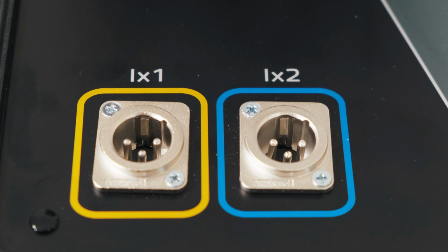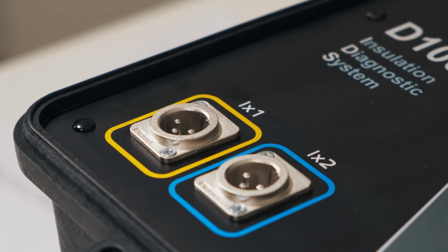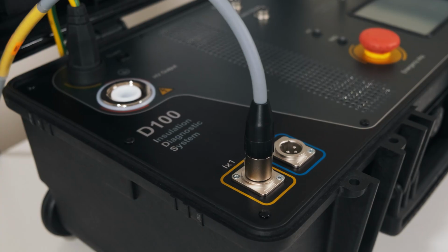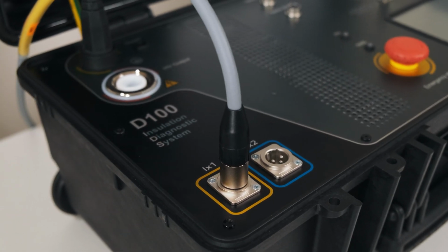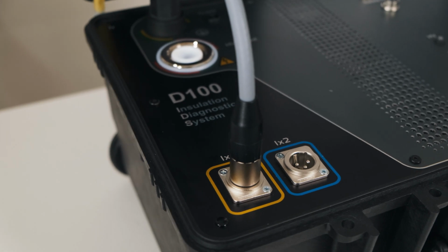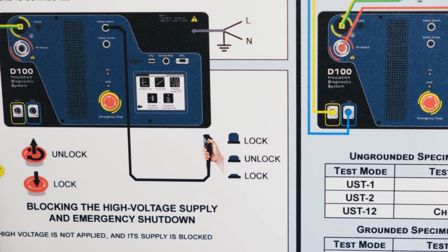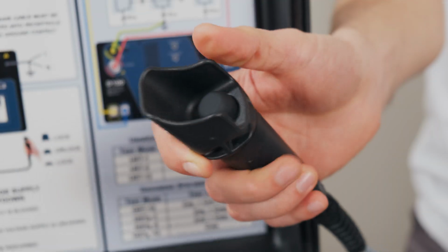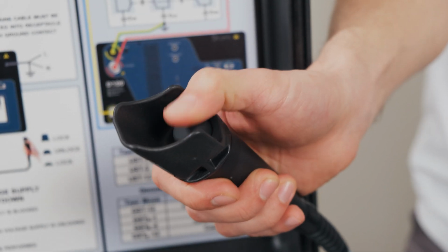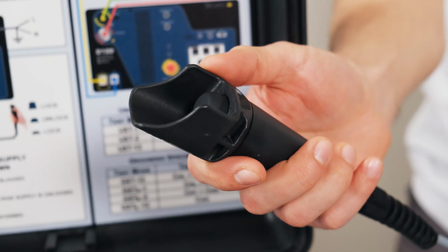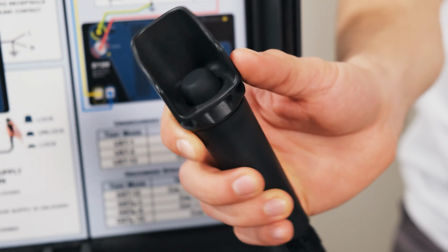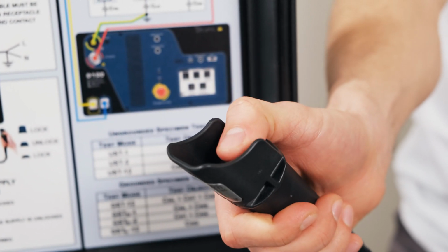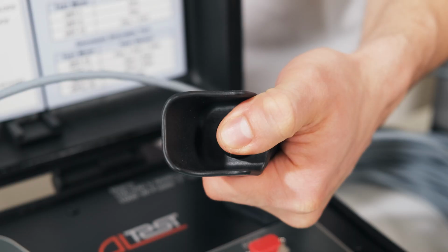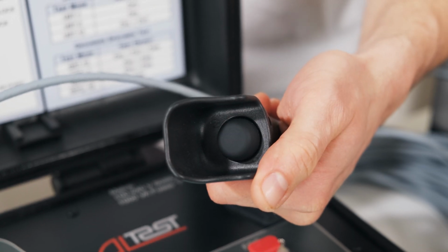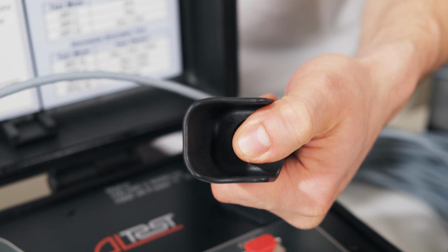There are two measuring connectors on the front panel of the device, IX1 and IX2. Depending on the test mode, you must connect one or two cables. A safety switch is provided to ensure personnel safety. The instrument won't work if the cable with this switch is not connected to the corresponding connector on the front panel of the device. If the switch is initially released or is absent, the high-voltage supply is locked. Press the switch to unlock it.